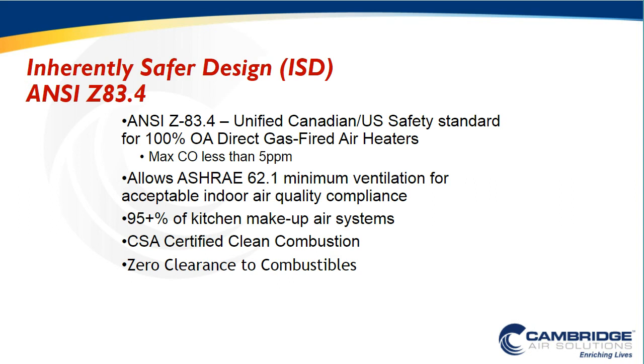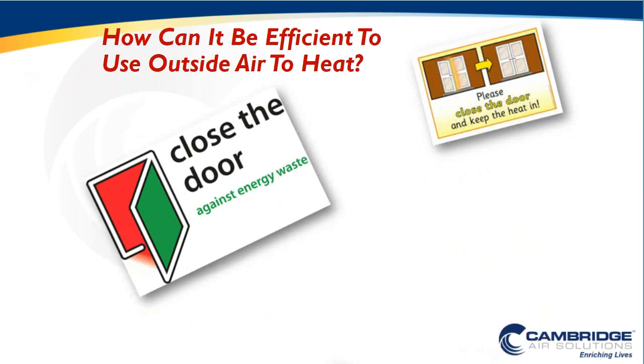For those that are unfamiliar with the safety standard, what it does is certify that all of these products and all of these systems are able to achieve less than 5 parts per million CO added concentration. So in a worst case scenario, if we have 7, 8, or 9 parts per million outdoor air CO, the highest that the system can ever provide is 5 plus that, so 5 plus 9, 14, and we can never reach any levels above our discharge. So we will always be ventilating and always lowering the CO levels inside the space. So that's our safety component of the presentation today.